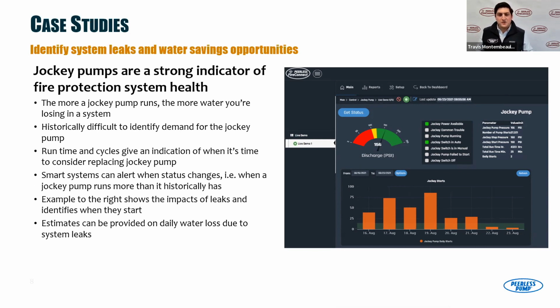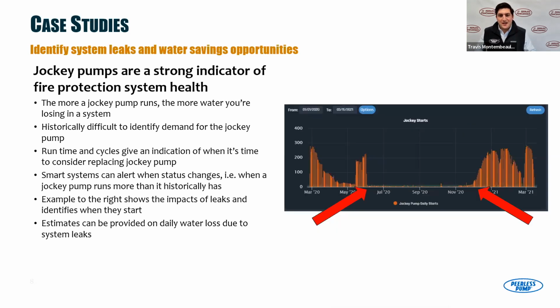And so we can do things like set an alert. If we know your jockey pump starts 25 times per day on average, we can set a threshold that says, send me a text message if it starts 35 times in a 24-hour period. And then you get an indicator that something may be changing here. And that becomes important when you start to look at 1-year performance charts like this. Each vertical bar is a 24-hour period of starts.